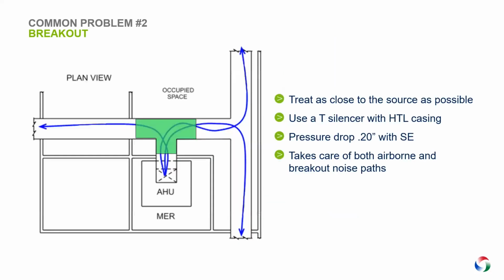To control that, we will actually need this T-shaped silencer, which is going to take care of both the airborne noise and the breakout noise, which will also serve as a T-shaped duct and will have a better performance and better pressure drop with system effect. Sometimes based on our analysis, we will recommend a T-shaped silencer or any other silencer with an HTL casing to control the breakout noise. And HTL casing is a high transmission loss casing, which is basically a thicker casing on the outside of the silencer to make sure that noise is not going to bypass the casing itself.